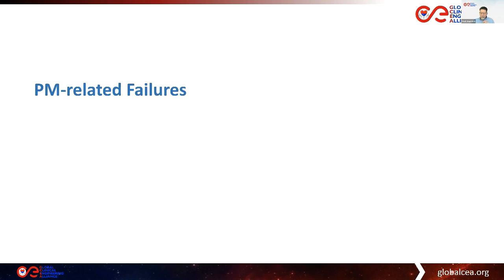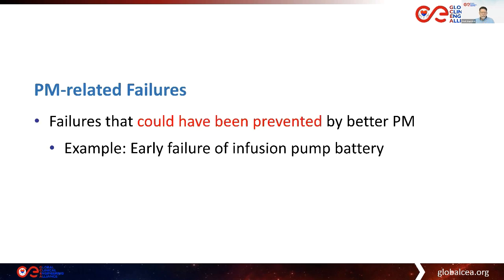Here are a couple of ways things are related to the PM program itself. Anytime we find a failure that could have been prevented by better PM, that's a PM-related failure. For example, with that infusion pump, if there's an early failure in the battery and it comes to our shop needing repair or corrective maintenance, maybe that could have been prevented by better PM, meaning changing the battery more often or buying a better quality replacement battery. So one aspect of PM-related failures is failures that could have been prevented by changes in our PM program.